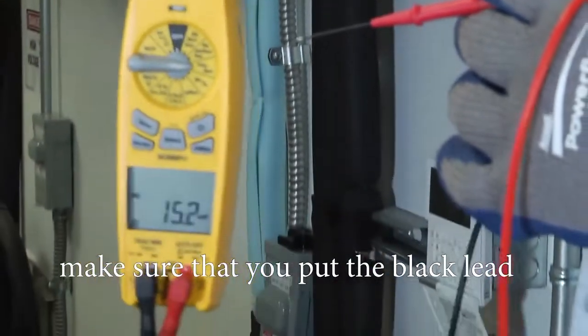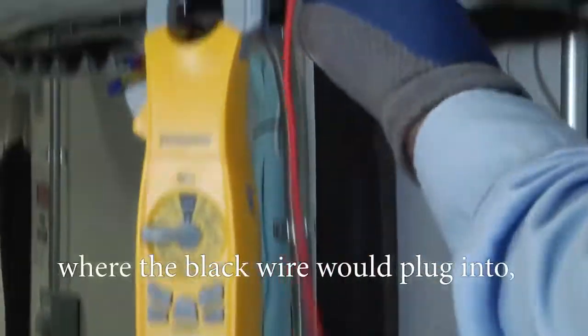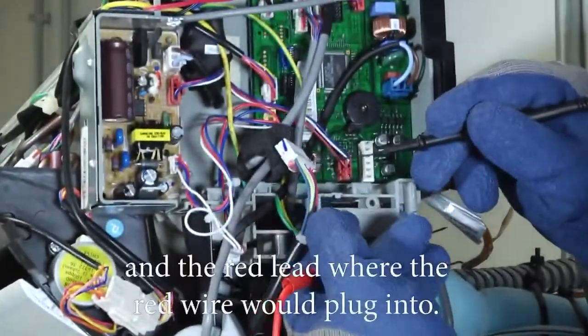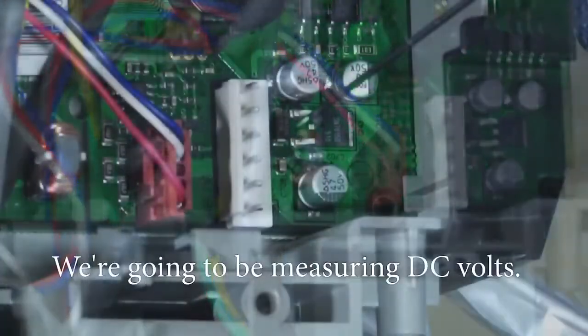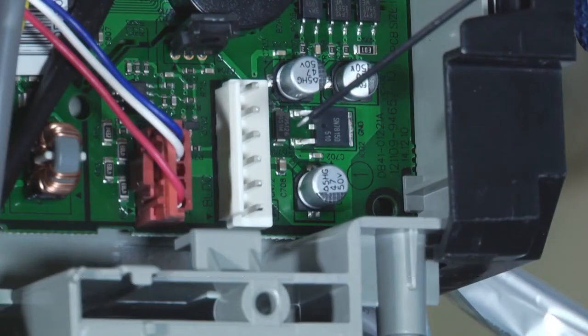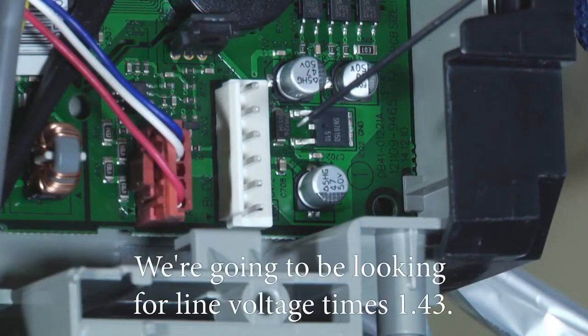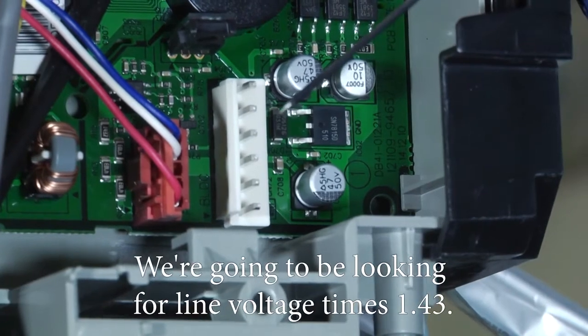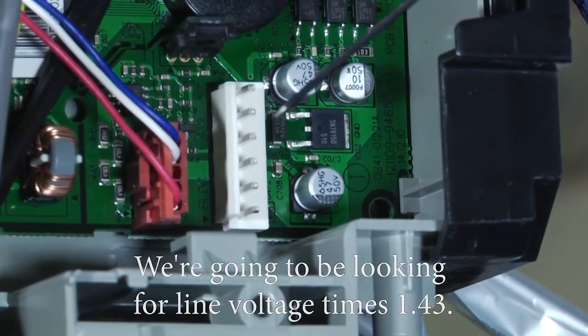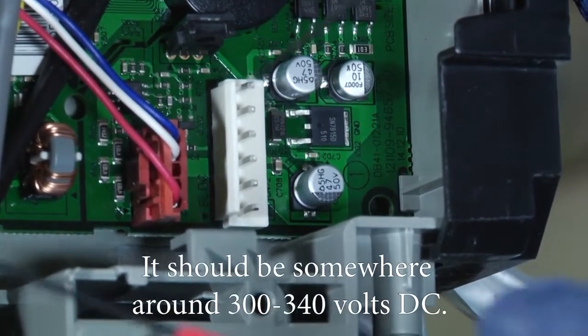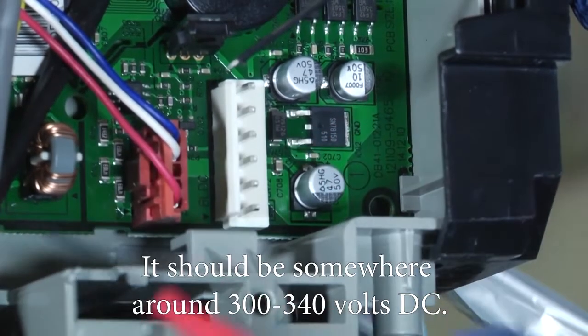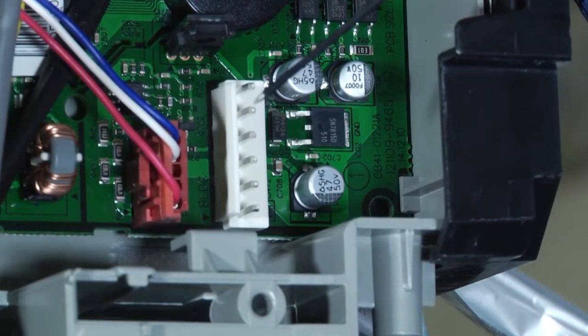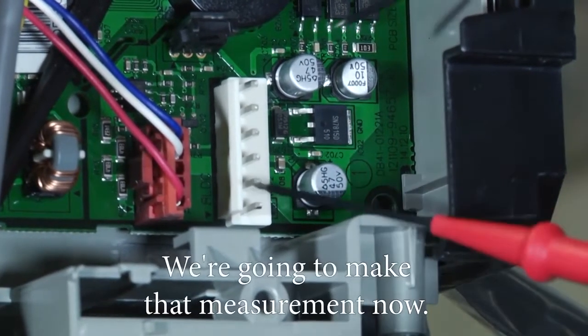We're going to be measuring DC volts. We're going to be looking for line voltage times 1.43. It should be somewhere around 300 to 340 volts DC. So we're going to make that measurement now.